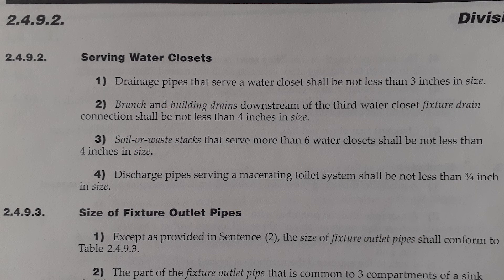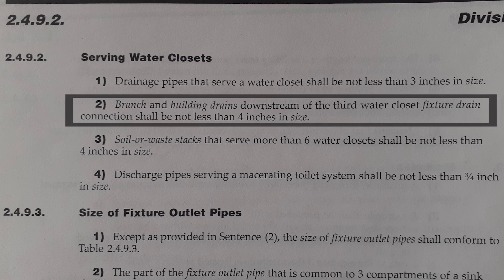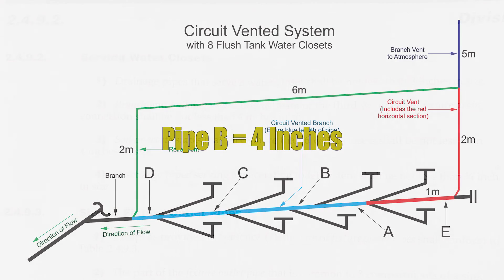Now we have a code clause to apply here. Clause 2-4-9-2 part 2 states that branch and building drains downstream of the third water closet fixture drain connection shall be not less than 4 inches in size. Therefore, pipe B by this clause needs to be 4 inches.